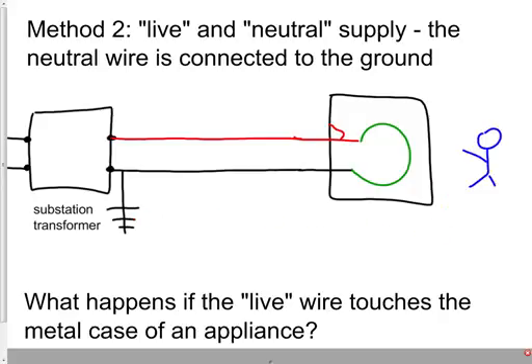So you might think, okay, what we could do is just connect the neutral wire. Let's branch off here with the neutral wire and also connect it to the metal case. That seems like a good idea, because watch what happens. If a bit of live wire somehow becomes detached and touches the metal case, a big current flows through the metal case, back through the neutral wire, and the fuse blows. So the fuse inside the plug for this appliance blows, and we're safe. Okay, if the live wire touches the case, big current flows, fuse blows, we're safe. This seems pretty good basically.